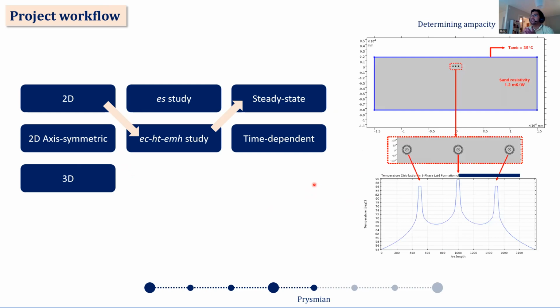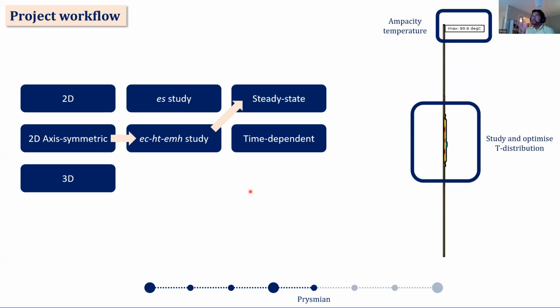The second study was an electromagnetic heating study, a multiphysics approach coupling electric currents and heat physics. At steady state, for the cable system I was designing, I first determined the ampacity - I can't share the actual value since that's confidential. Then you go back to the axisymmetric model of the cable joint, pass the same current through it, check if the XLPE is at 90 degrees (the ampacity limit), and study the temperature distribution within the cable joint.